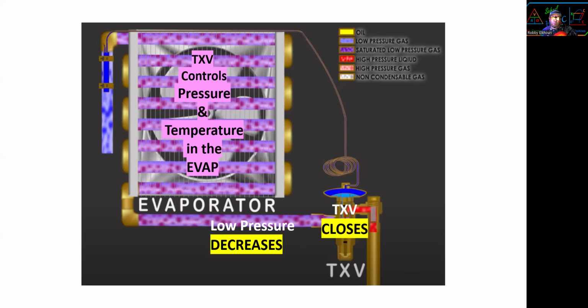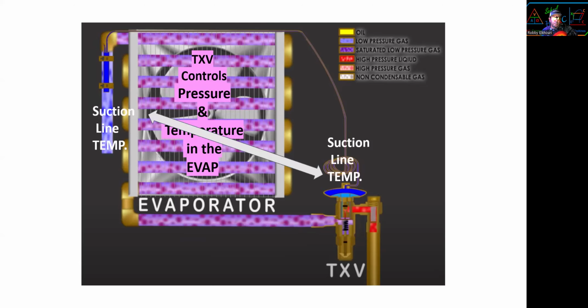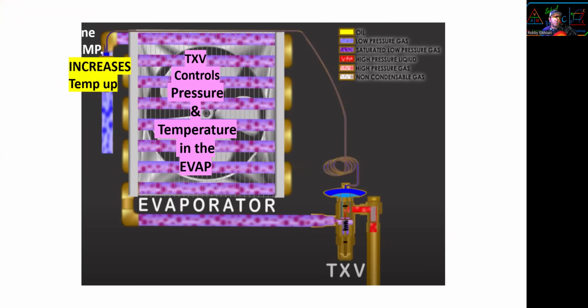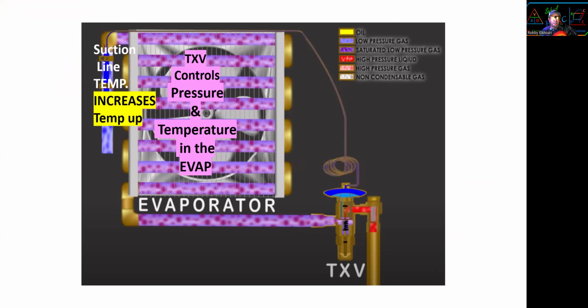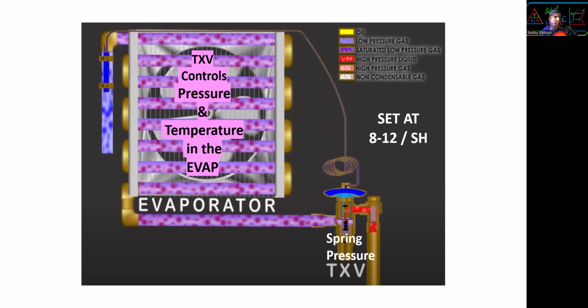The TXV controls pressure and temperature in the evaporator. Technically, only controls pressure, because temperature, it varies when you open the door. Temperature changes. Technically, the proper way is controls only pressure. Alrighty. So now, when we have low pressure, when the pressure decreases, the TXV will close. Suction line temperature will affect the diaphragm. Suction line temperature increases, temperature will go up. The TXV will open.